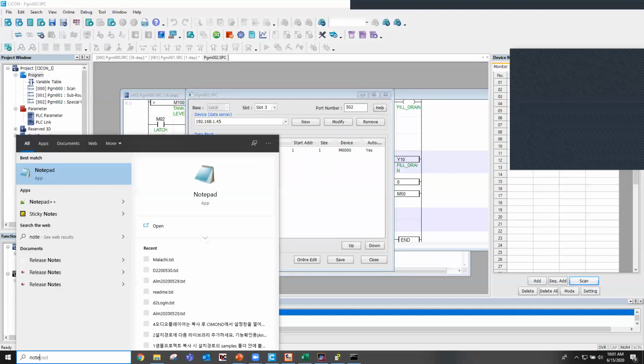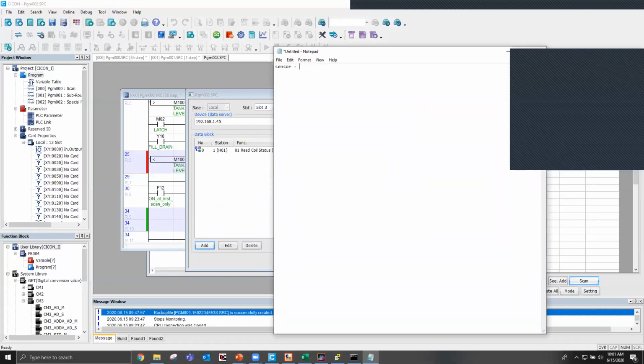So let me write that on Notepad real quick. So the sensor is talking through Modbus to the PLC, and then the PLC is taking, let's just say, Modbus register 1, and the PLC is using a send or receive command to target this function right here, and it's taking Modbus register 0001 and then inputting it into M000. So all you have to do is essentially make a Modbus master program, and tell the data register for Modbus to be pointed at a device register within the PLC. It looks a little bit complicated, but it's really not.